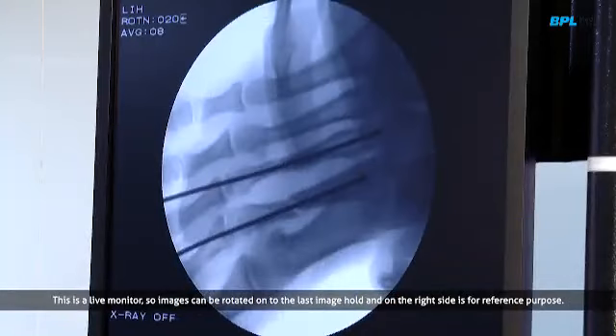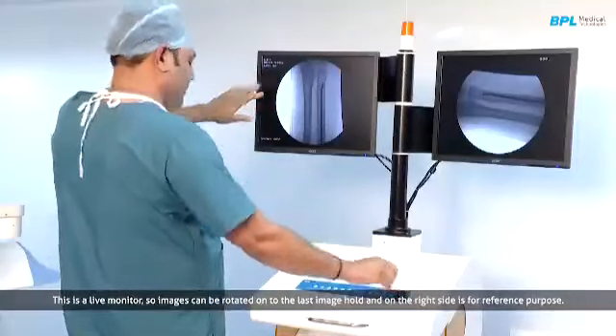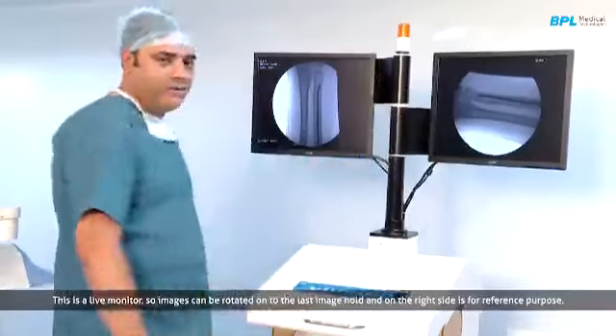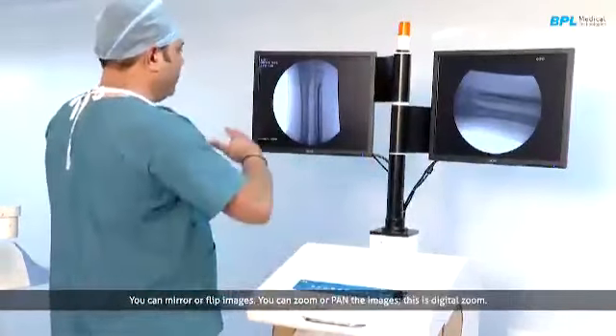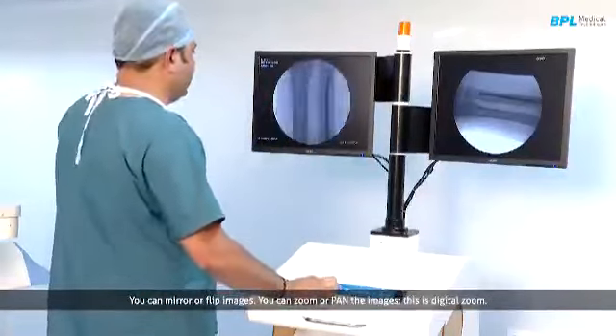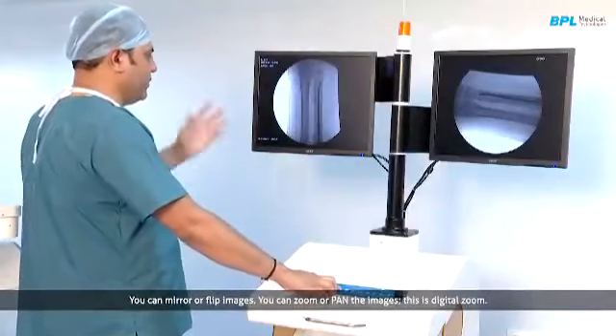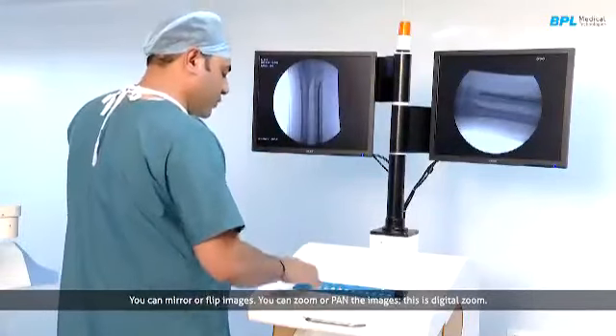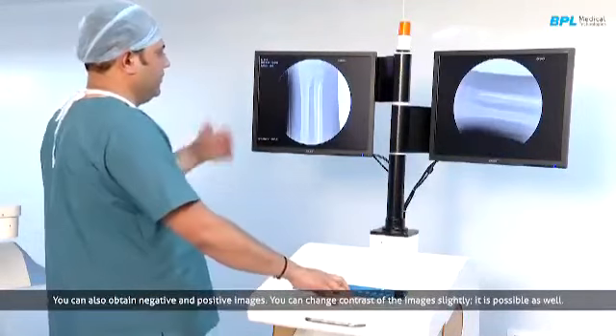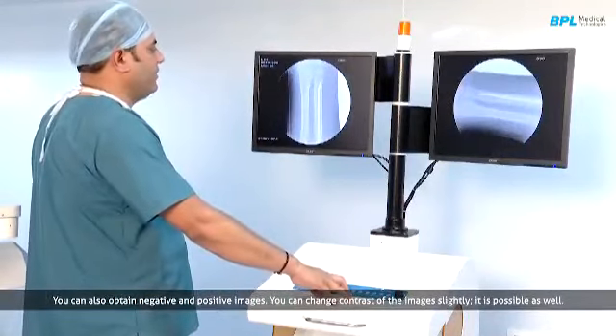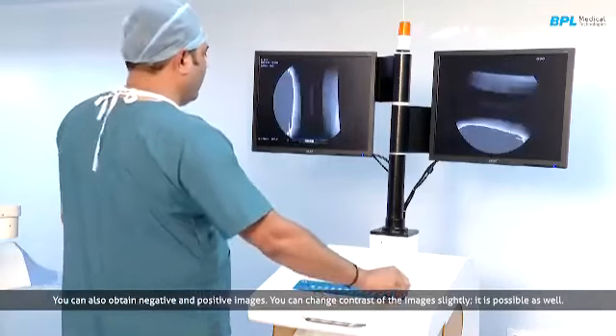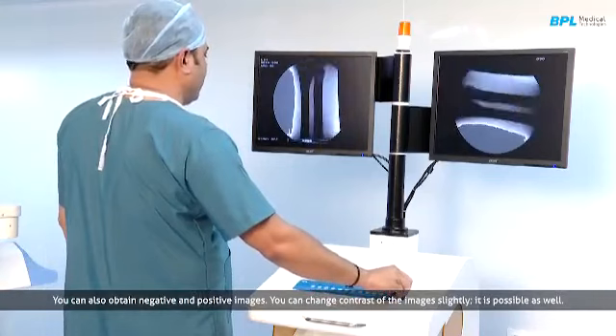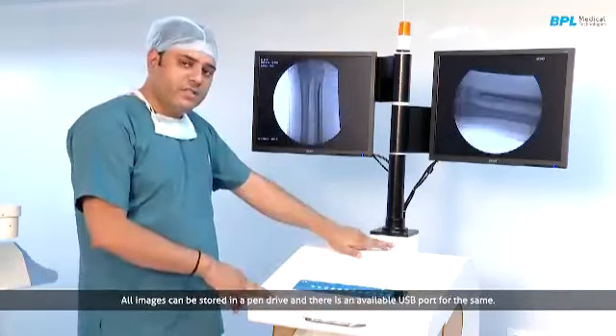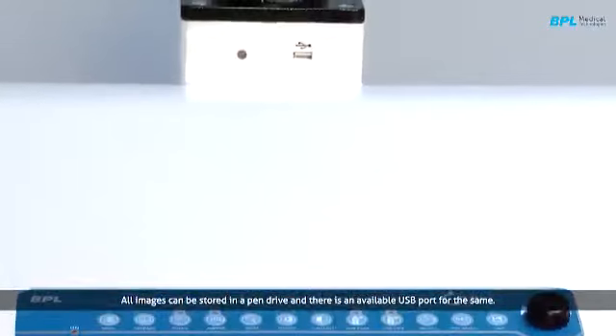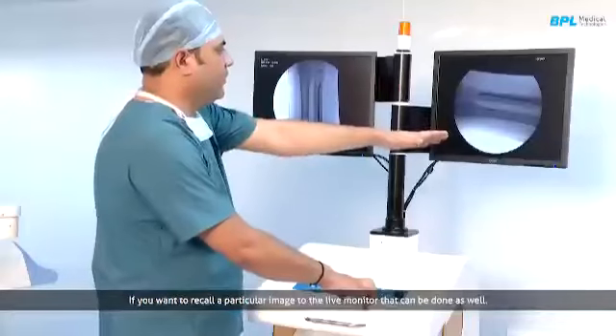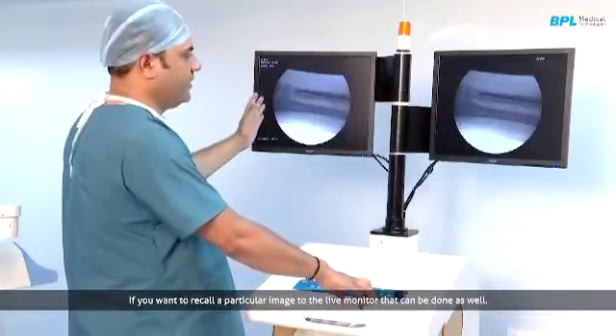And this is the live monitor, so you can rotate it onto the last image hold, and the right side is for reference purposes. Then you can do mirror or flip. You can zoom and pan the images. This is digital zoom, and you can do negative, and this is positive. If you want to slightly change the contrast, it is possible to change the contrast as well. All the images can be stored on a pen drive, and there is a USB port for that. If you want to recall this image to the live monitors, yes, it is recalled now.